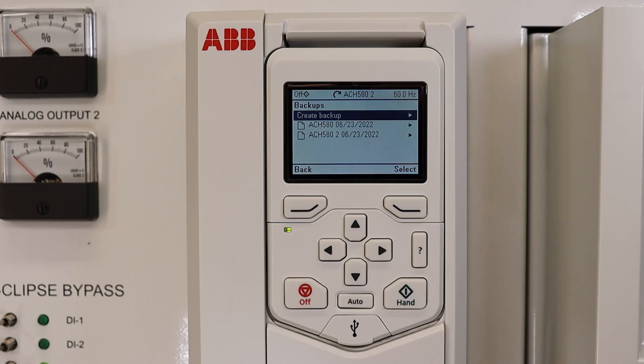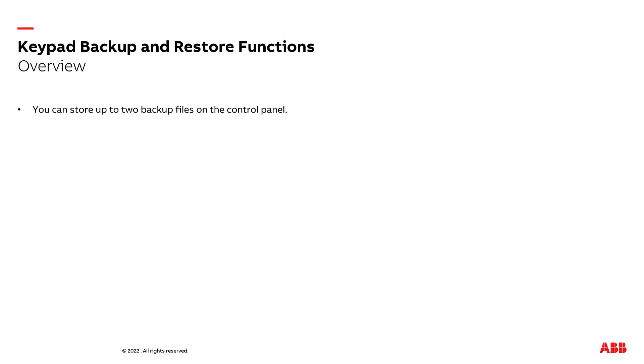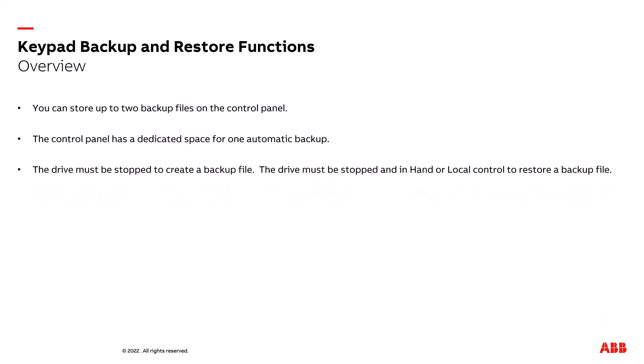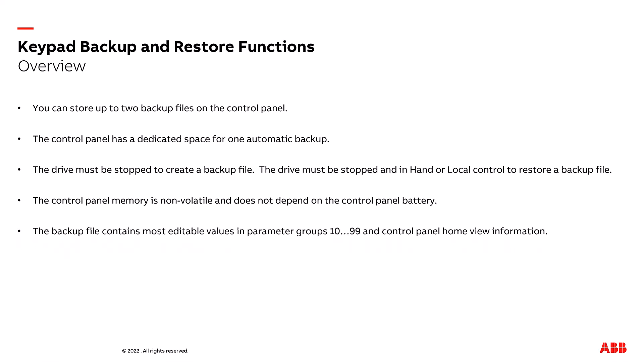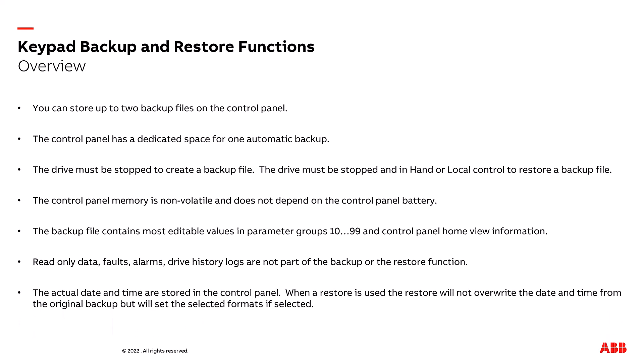Let's take a look at what you can do with these backup files. You can store two backup files on the control panel. The control panel has a dedicated space for one automatic backup. The drive must be stopped to create a backup file, and must be stopped and in hand or local control to restore a backup file. The control panel memory is non-volatile and does not depend on the control panel battery. The backup file contains most editable values from parameter groups 10 through 99 and the control panel home view information. Read-only data, faults and alarms, and drive history logs are not part of the backup or restore function. The actual date and time is stored on the control panel.